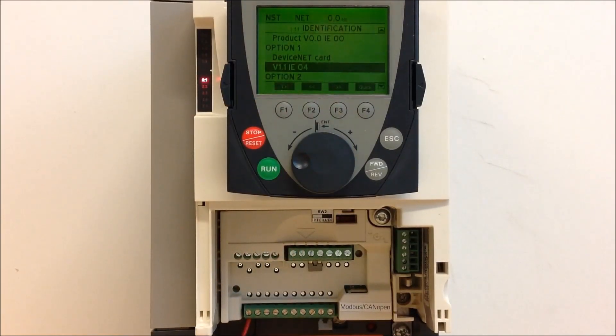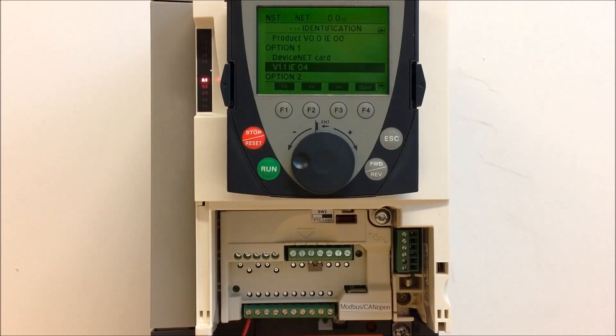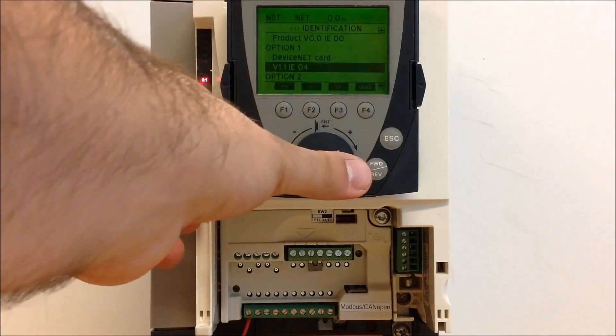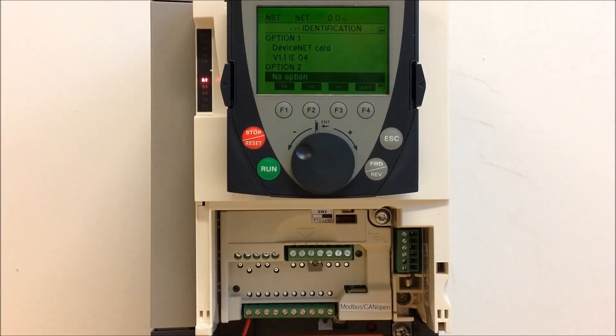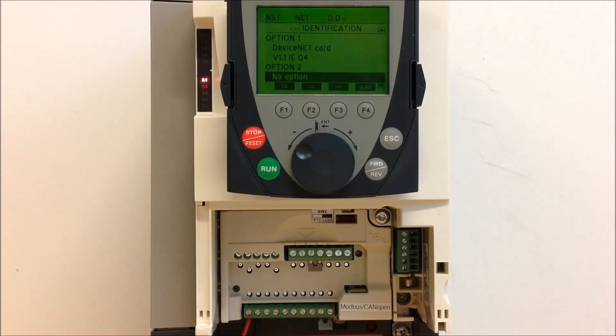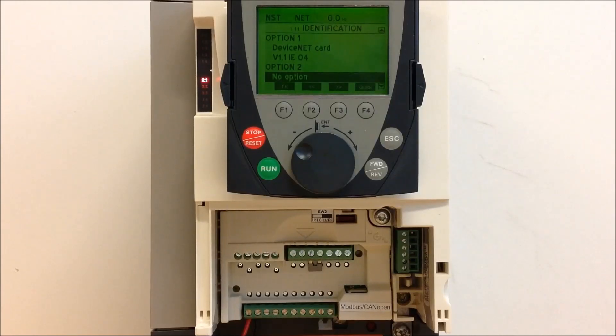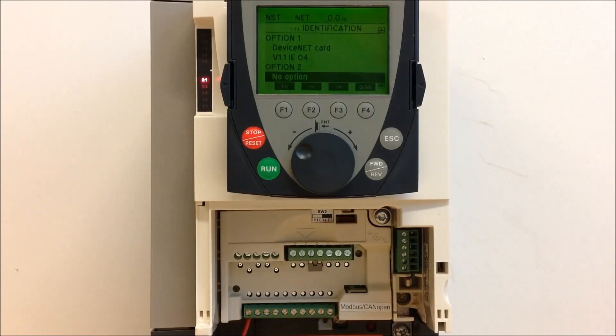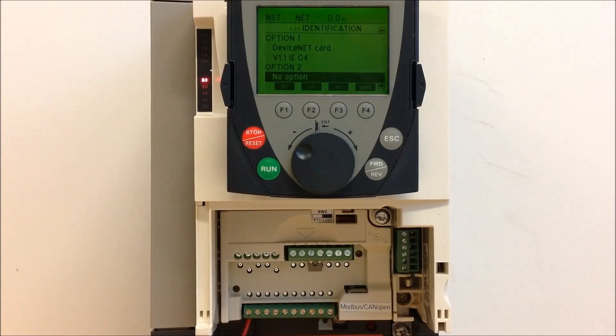It will tell you that the firmware version of that card is 1.1 IE04 as an example. And for option 2, we have no options, so you only have one option card installed at the moment for this particular drive as an example. This is how you basically confirm what option cards you have on the ATV61 and 71 drives.